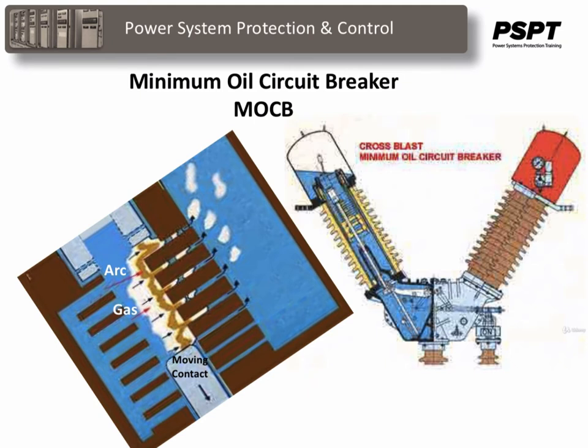The axial venting generates high gas pressure and hence has high dielectric strength, so it is mainly used for interrupting low electric current at high voltages. On the other hand, radial venting minimum oil circuit breakers produce relatively low gas pressure and hence low dielectric strength, so they can be used for low voltage and high electric current interruption. Many times, a combination of both is used in minimum oil circuit breakers so that the chamber is equally efficient at interrupting low electric currents as well as high electric currents. These types of circuit breakers are available up to 8,000 MVA at 245 kV.